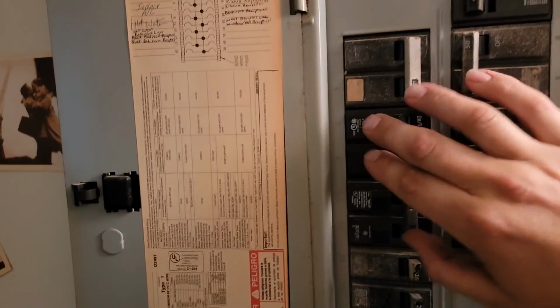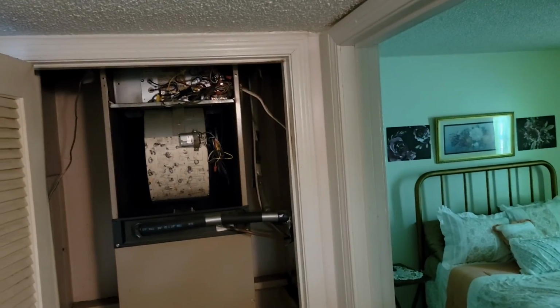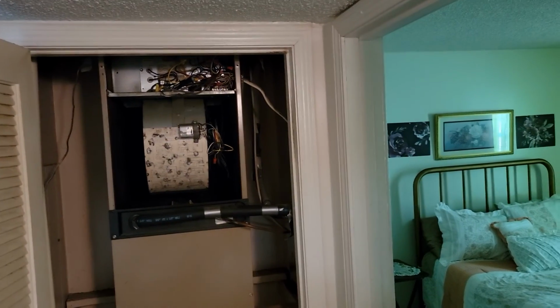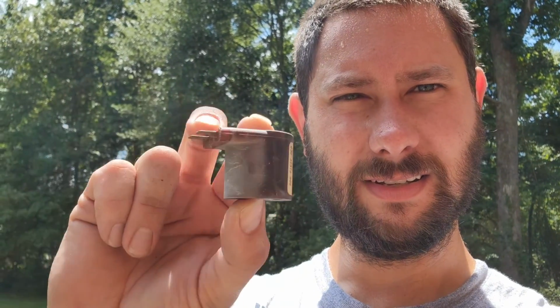Moment of truth. Did we find the short? We found the short. It's in the reversing valve coil. All right. Cause and effect. This was the cause that affected the transformer.